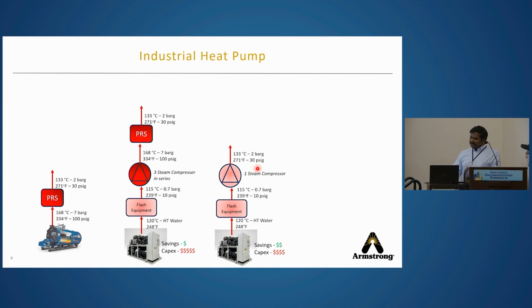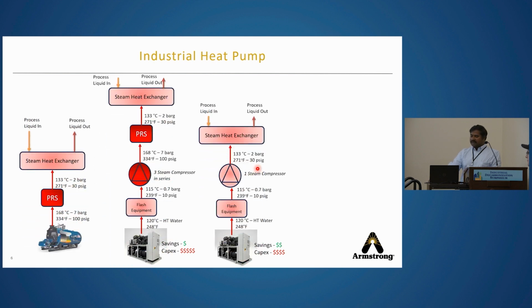Then we really ask the customer, can you open up and tell us what your actual application is? They say that they take this 30 PSI of steam into a steam heat exchanger and heat the process liquid only up to 158 degrees Fahrenheit. To heat a process liquid to 158 degrees Fahrenheit, why do they need a steam heat pump? That to 100 PSI, reduced to 30 PSI.